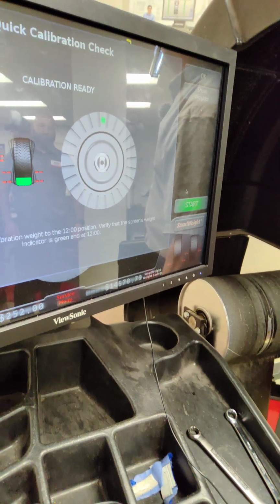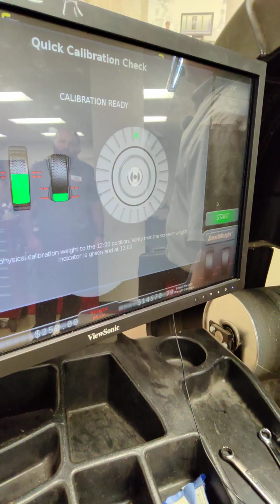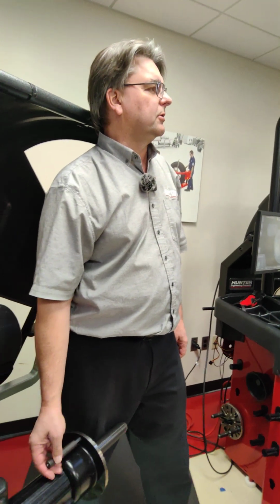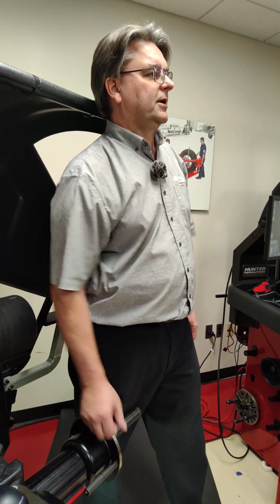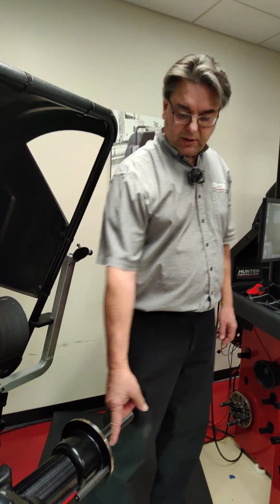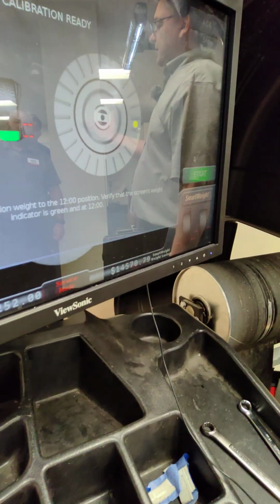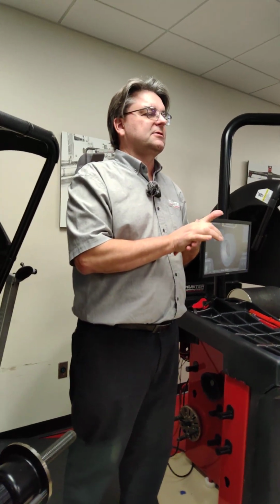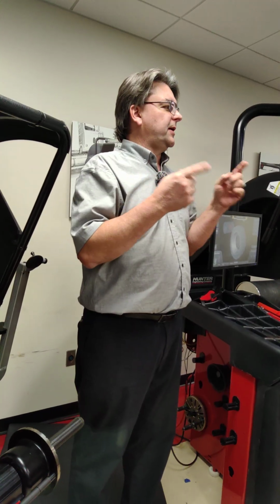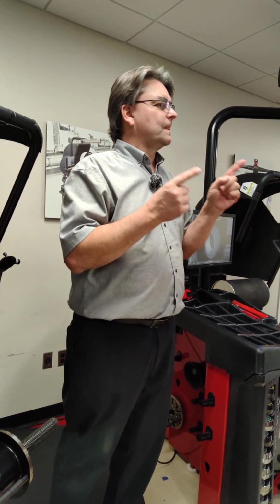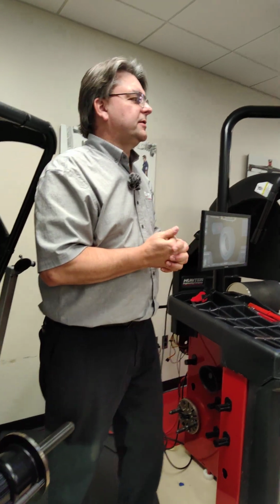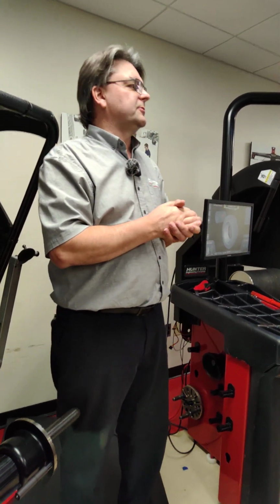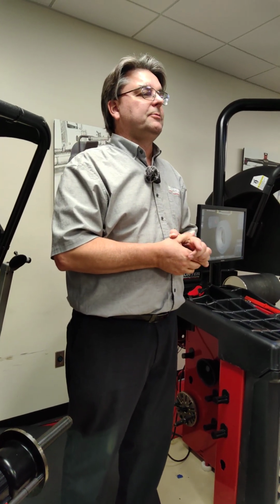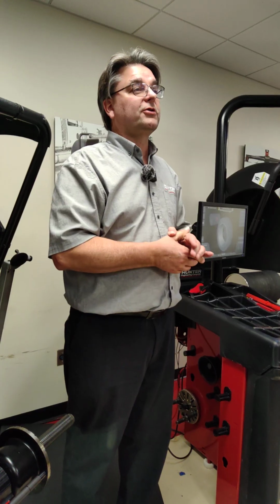And what's really important is that's telling you that whoever calibrated this thing calibrated it with 12 o'clock actually at 12 o'clock. You're going to go into a lot of places and the green dot is going to turn green and this thing is going to be way over there. Now when this is way over there and the green dot is actually green, every person who ever calls you is going to have one of 2 complaints. It's either going to be a complaint that the thing doesn't spin, or the other complaint you're going to hear is that the balancer is chasing weights. Okay, about 90% of the calls you get on a balancer is going to be a chasing weights call. 90% of that 90% is something, so someone is doing something wrong or did something stupid.